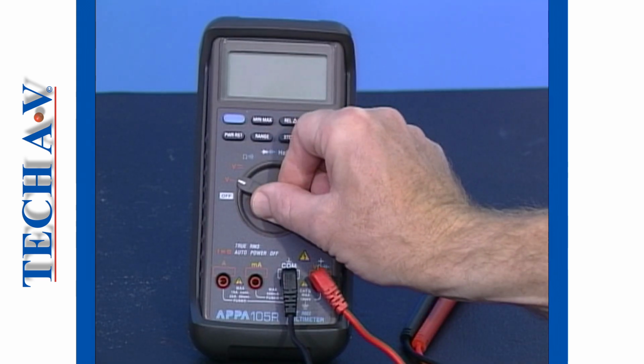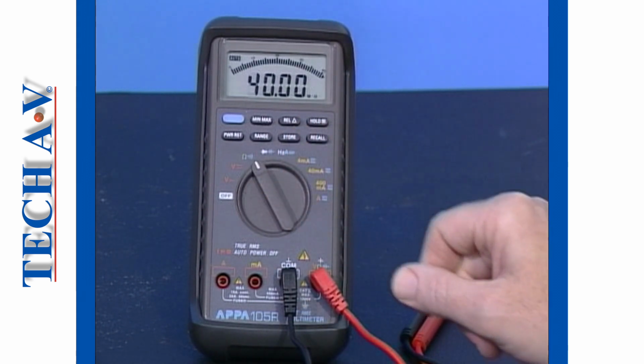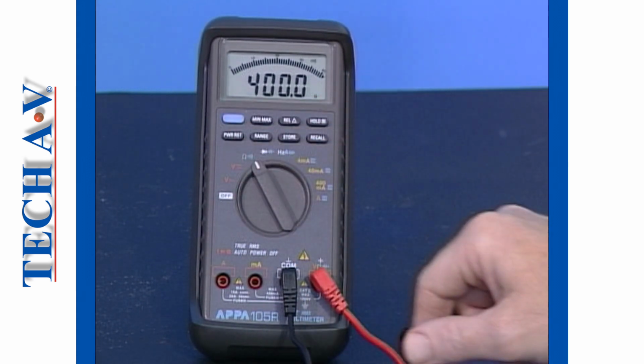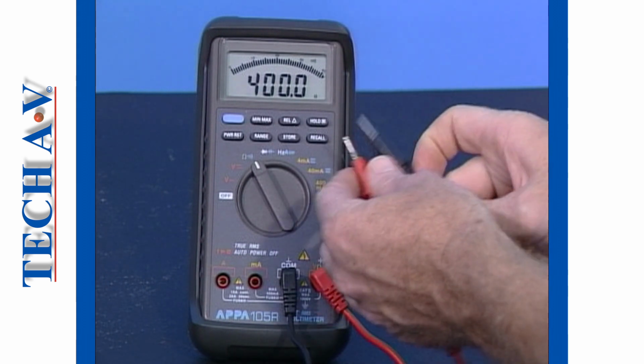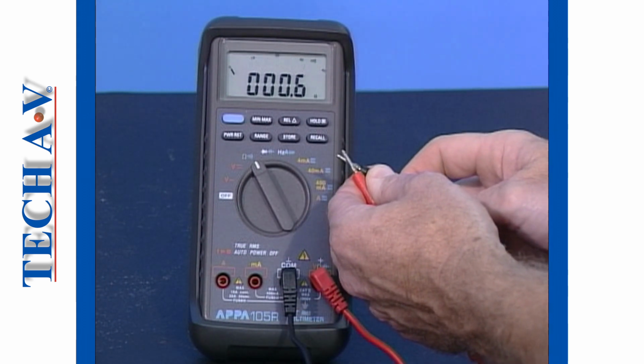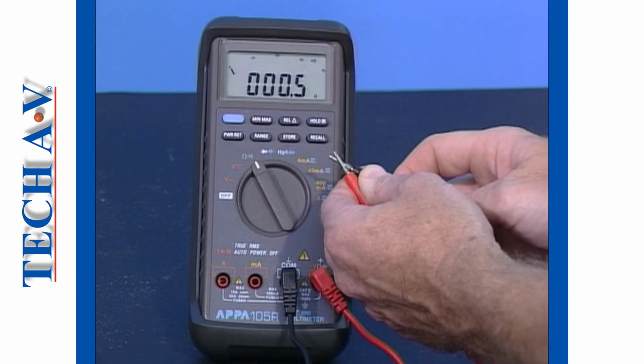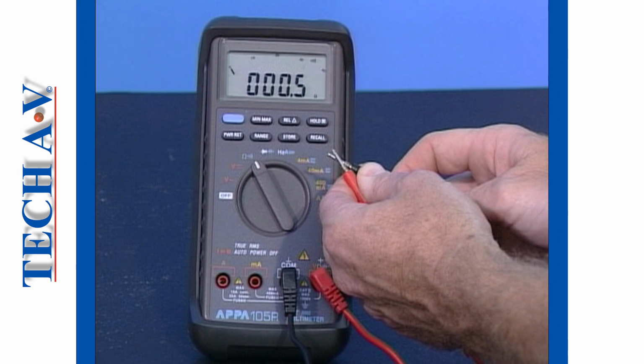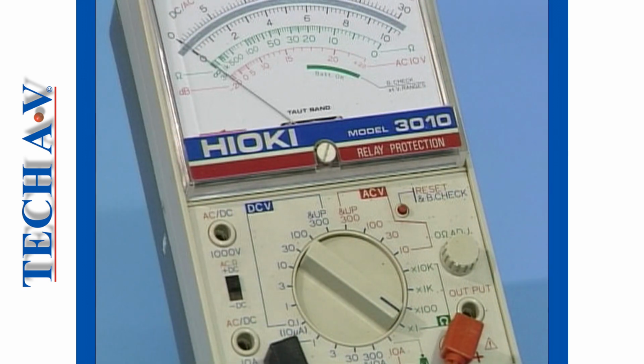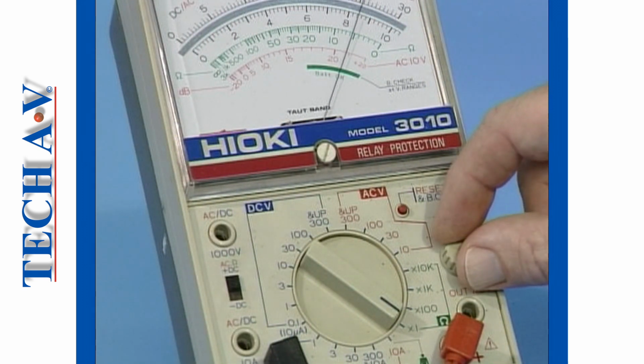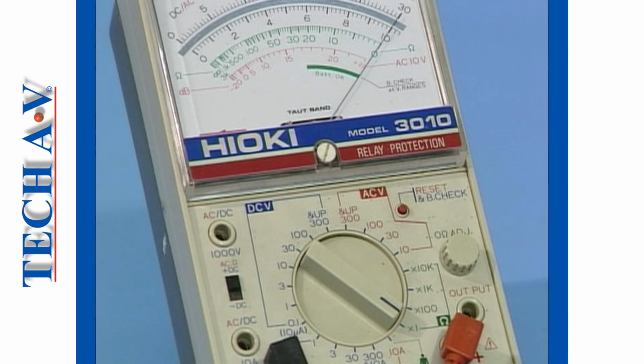Begin by setting the multimeter to the low ohm setting. Check the 0 ohm calibration by shorting the probes together and noting the meter reading, which should be 0 ohms, excluding the resistance of the test leads. When using an analog type multimeter, turn the adjustment control until the meter needle lines up with the 0 ohm mark on the ohm scale.